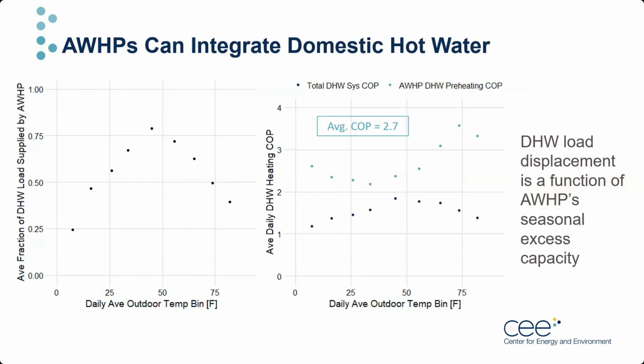After the scatter plots that we've just seen, it's maybe a welcome change that these are nice, clean profiles that we can look at. On the left, we have a chart for the average fraction of domestic hot water load supplied by the heat pump plotted versus outside air temperature. On the right, we have average daily domestic hot water heating COP for the overall system in navy, and for the heat pump alone in teal, also plotted against daily average OAT.